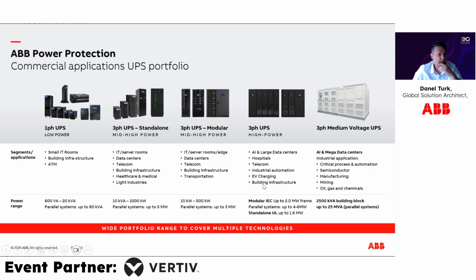Remembering the earlier slide with the different day 1, 2, 3, 0 networks, utilizing a medium voltage UPS means moving away from low voltage to medium voltage level. This helps keep your site future-proof, because whatever technology you use later in different rack sizes, whether DC or different DC voltage levels, if you've already installed your medium voltage UPS, it doesn't matter how you design your last mile.